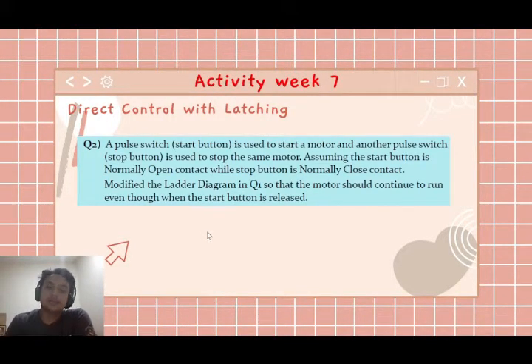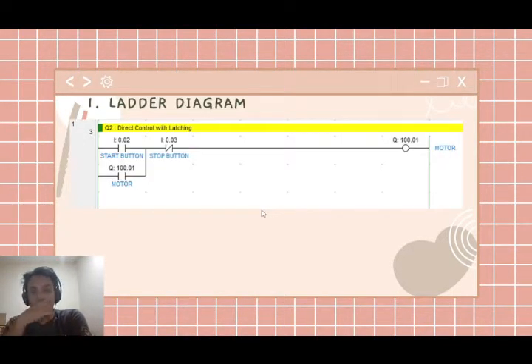Second, we have direct control with latching. A push switch start button is used to start a motor, and another push switch stop button is used to stop the same motor. Assuming the start button is a normally open contact while the stop button is a normally closed contact, modify the ladder diagram in Q1 so that the motor continues to run even when the start button is released. This is the ladder diagram for direct control with latching.